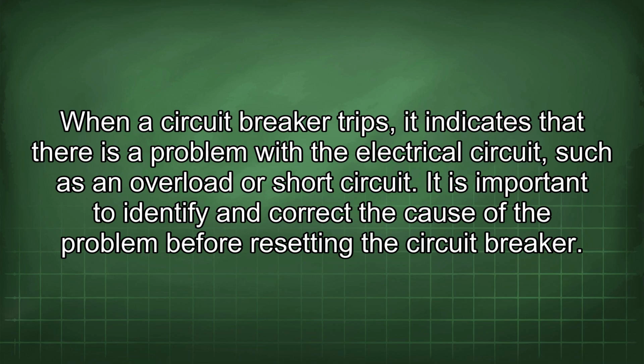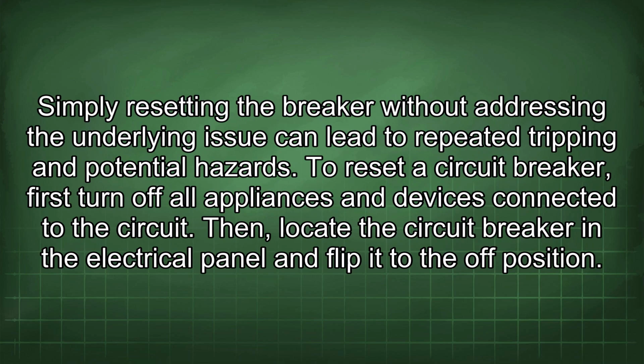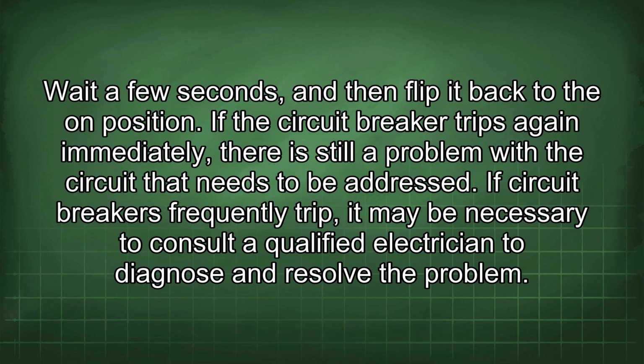When a circuit breaker trips, it indicates that there is a problem with the electrical circuit, such as an overload or short circuit. It is important to identify and correct the cause of the problem before resetting the circuit breaker. Simply resetting the breaker without addressing the underlying issue can lead to repeated tripping and potential hazards. To reset a circuit breaker, first turn off all appliances and devices connected to the circuit. Then locate the circuit breaker in the electrical panel and flip it to the off position. Wait a few seconds and then flip it back to the on position. If the circuit breaker trips again immediately, there is still a problem with the circuit that needs to be addressed. If circuit breakers frequently trip, it may be necessary to consult a qualified electrician to diagnose and resolve the problem.